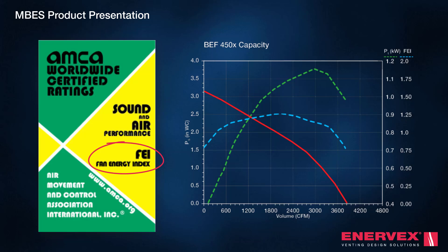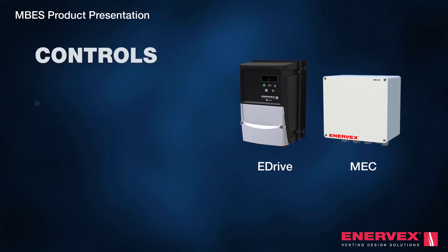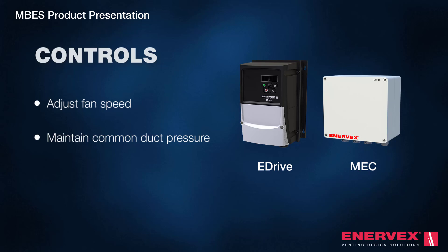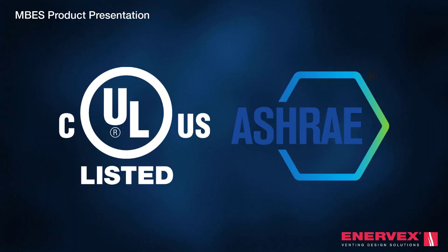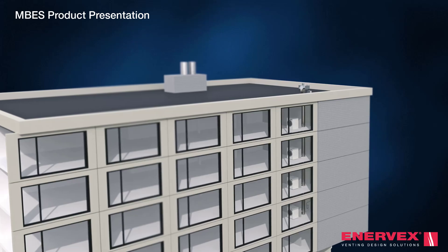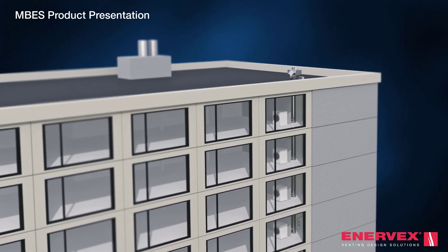It is also one of the few AMCA FEI rated centrifugal fans, with capacities up to 30,000 CFM. Equipped with EDrive and MEC controls to adjust fan speed and maintain common duct pressure, the exhaust system is constantly monitored ensuring optimal operation. It's a UL listed system that meets ASHRAE energy code 90.1 requirements.